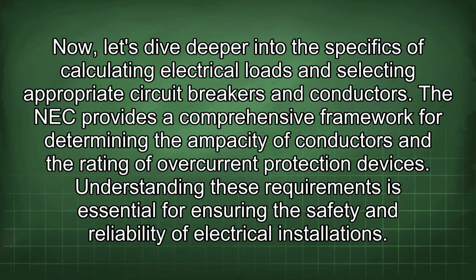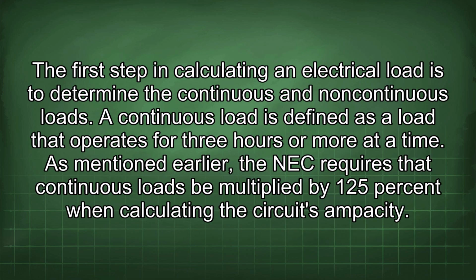The NEC provides a comprehensive framework for determining the ampacity of conductors and the rating of overcurrent protection devices. Understanding these requirements is essential for ensuring the safety and reliability of electrical installations. The first step in calculating an electrical load is to determine the continuous and non-continuous loads. A continuous load is defined as a load that operates for 3 hours or more at a time. As mentioned earlier, the NEC requires the continuous loads be multiplied by 125% when calculating the circuit's ampacity.